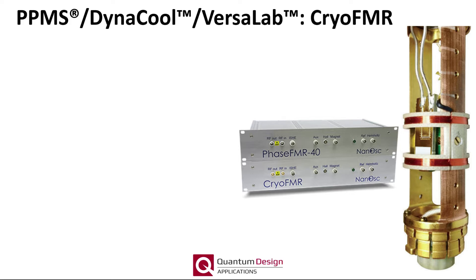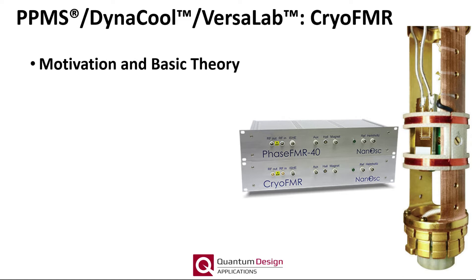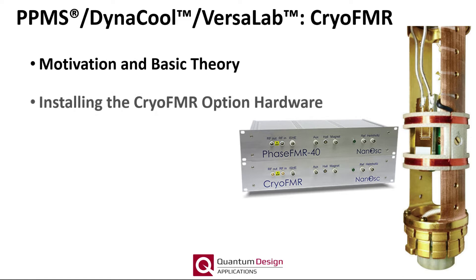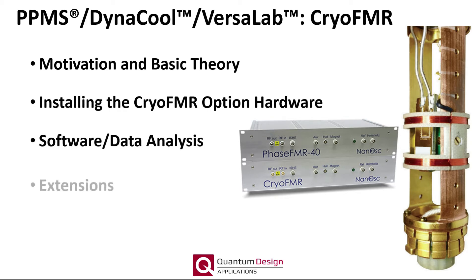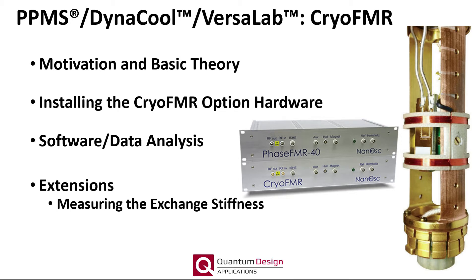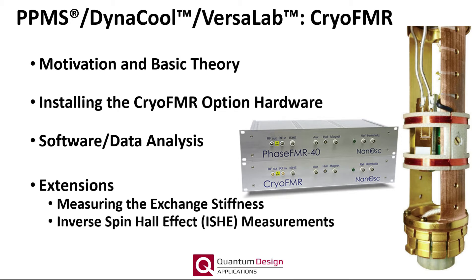The cryo-FMR option allows the experimenter the ability to probe the broadband ferromagnetic resonance, or FMR, properties of their samples, potentially spanning 2 to 40 GHz and at magnetic fields and temperatures offered by their base PPMS system. This webinar will cover the motivation and basic theory behind a broadband FMR measurement, installing the cryo-FMR option hardware, the software and subsequent data analysis, several extensions to our broadband FMR capabilities including how to measure the exchange stiffness, how to measure the inverse spin-Hall effect, and finally other measurement platforms in which broadband FMR can be performed using the electronics provided by NanOsc.